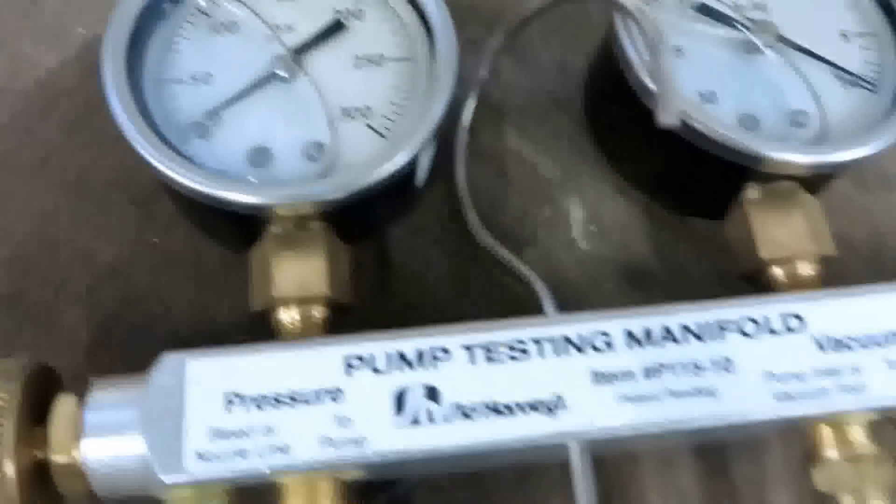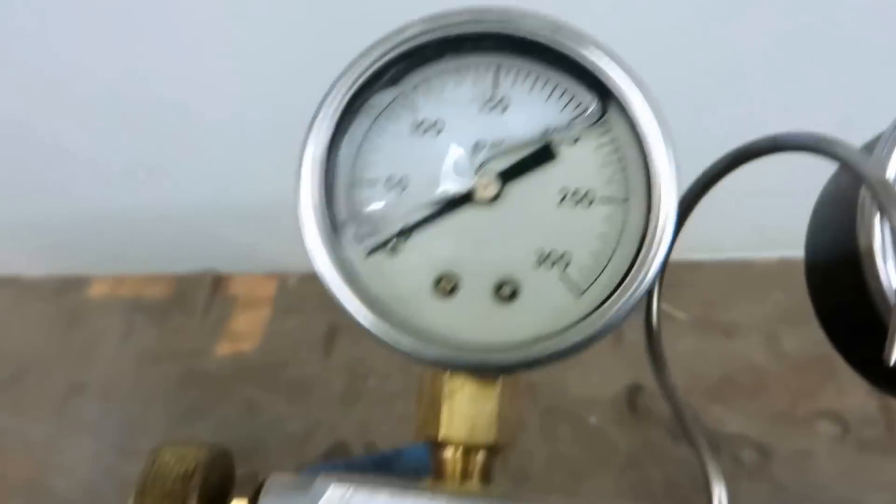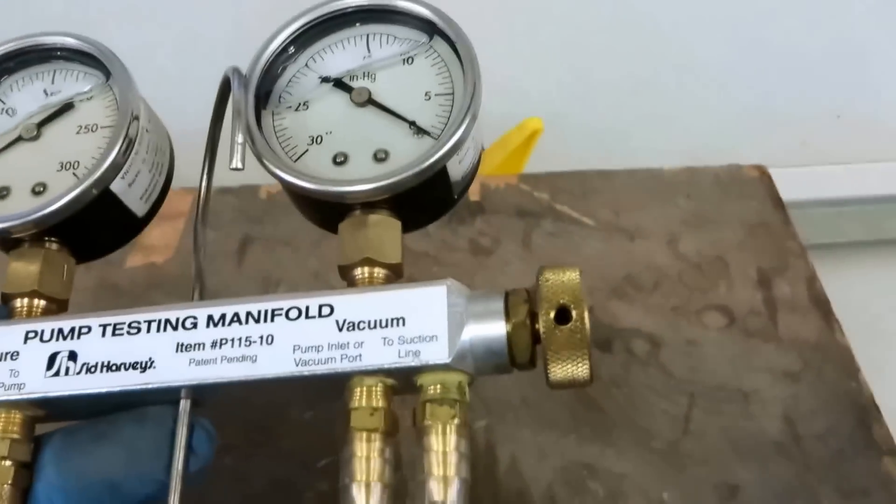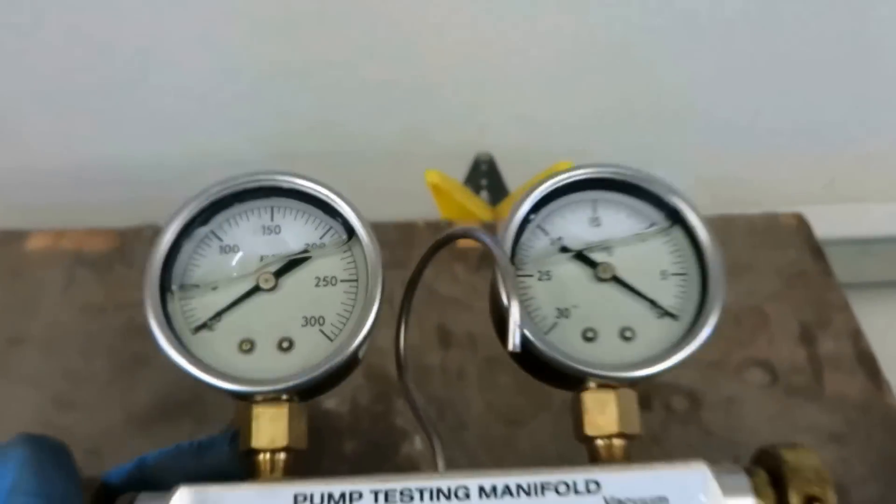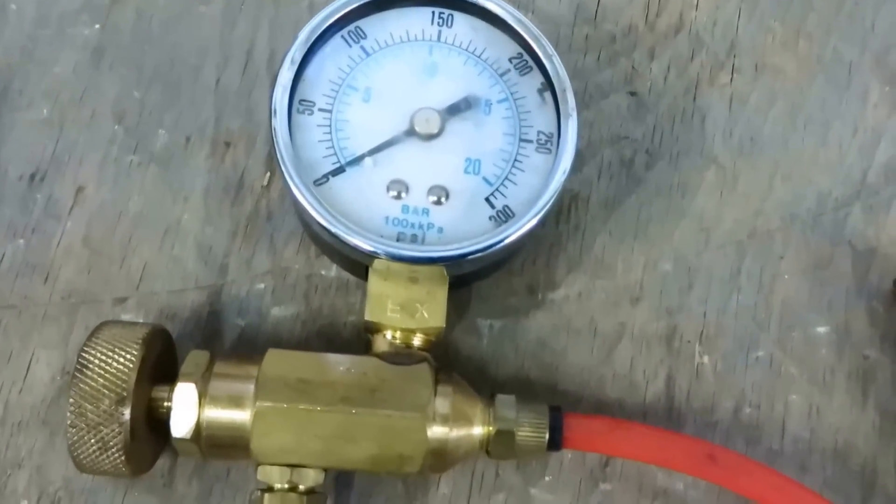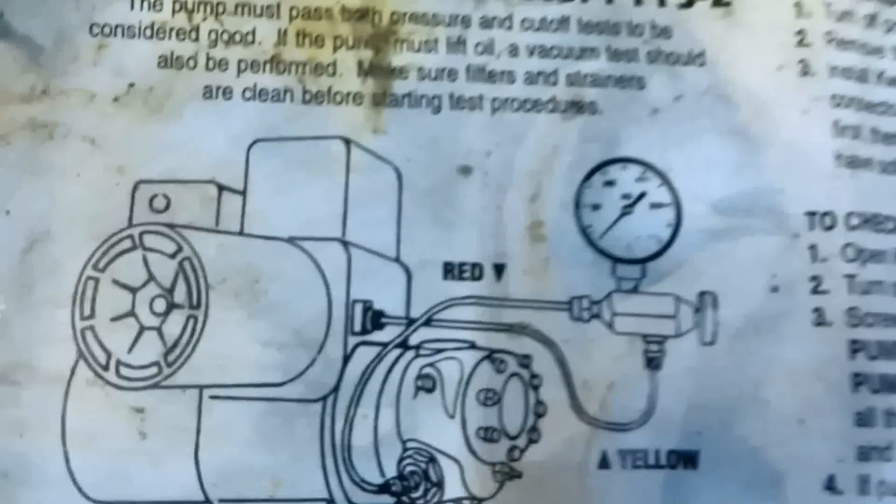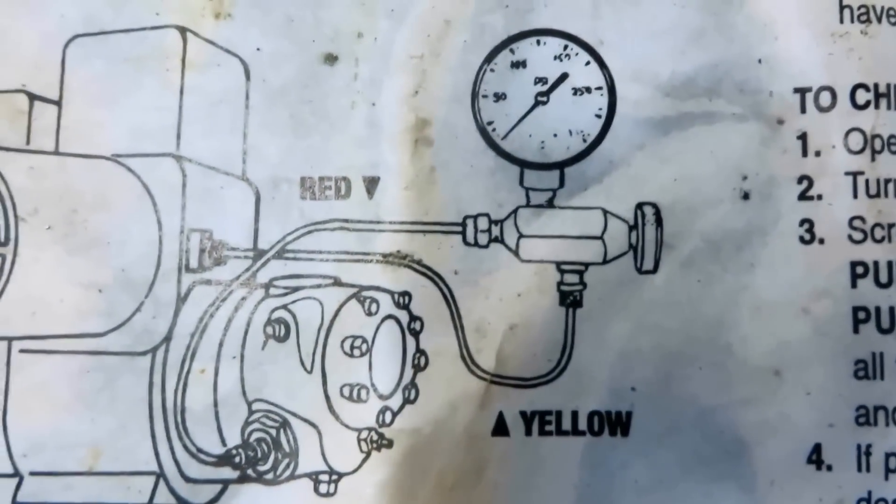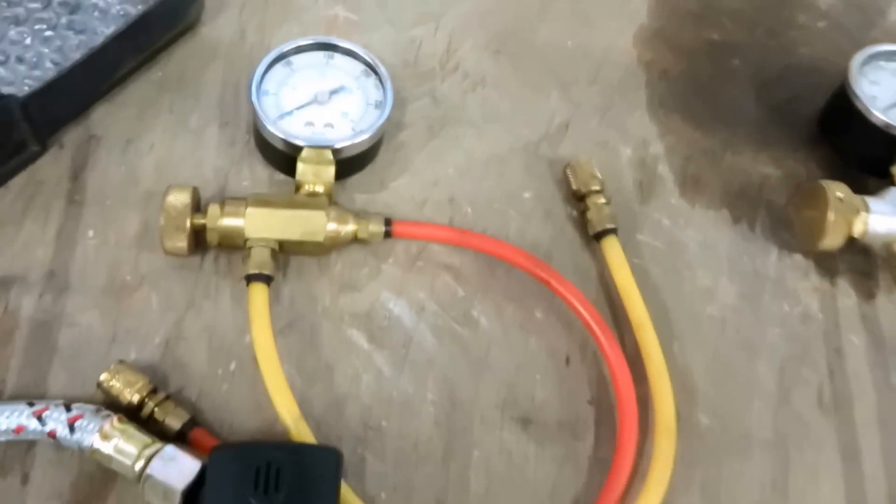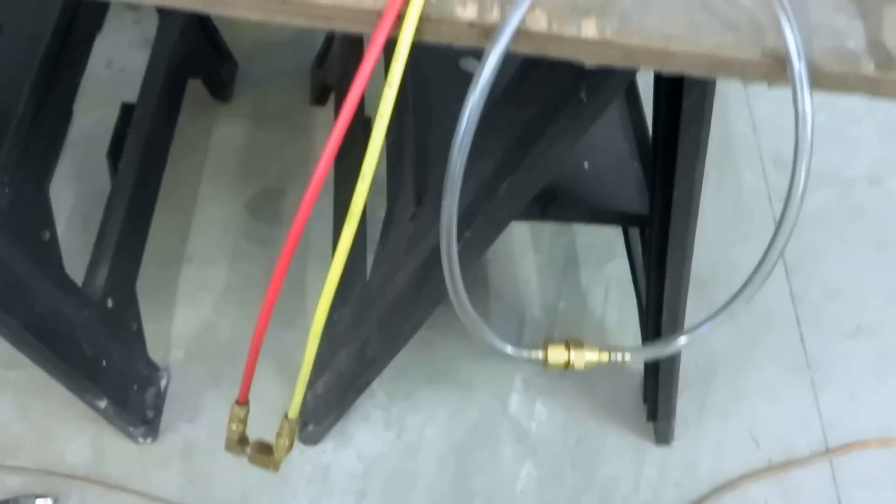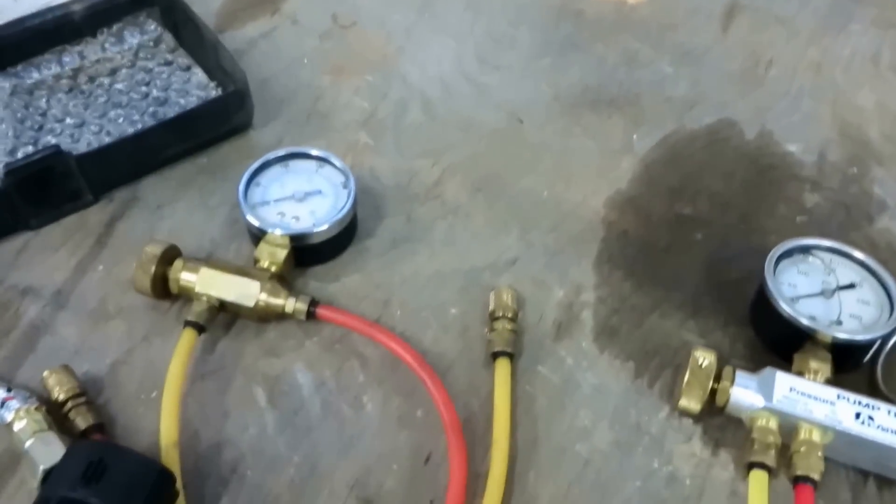For testing the pumps, I got this gauge here. It's like a manifold gauge, refrigerant gauge. Check the vacuum pressure coming into the pump and going out. And I can shut it off if I want. Use this sometimes on pumps. This one here is strictly just on the supply side of the pump. So you could actually run it and check the pressure at the same time which is pretty cool. Or I could just use my regular gauge like I usually do.